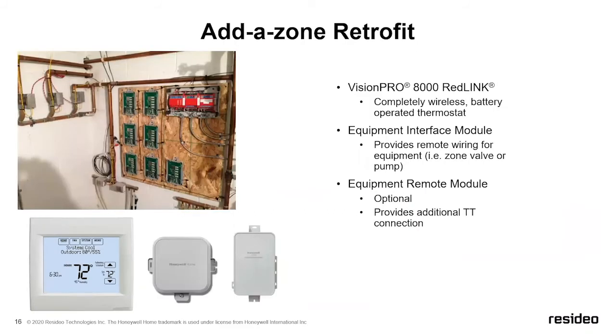I do want to talk about retrofit jobs. So I get the question more and more. It's coming up all the time as we're seeing an increased conversion into connected thermostats, Wi-Fi solutions, etc., where they've got an existing job. It was run with 2-strand wire, meaning that there's only 2 wires going to the thermostat. The problem is almost all of the options that are out there today require 3.